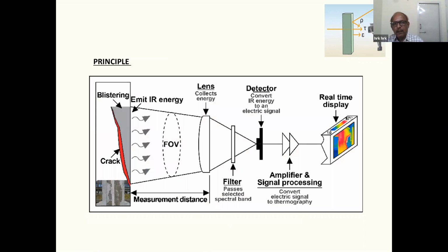This is the working principle of the thermal imager. For the first part, it works like an ordinary camera, measuring the field of vision. Infrared rays emitted from the field of vision are collected by the lens, then filtered by spectral band, typically from 7 to 14 micrometers. This falls on a substrate that generates an electrical signal, which is amplified and converted into temperature, then displayed on the screen.